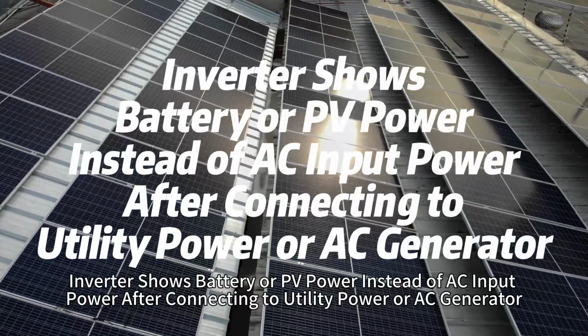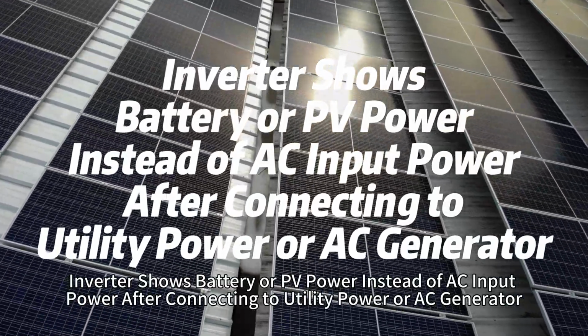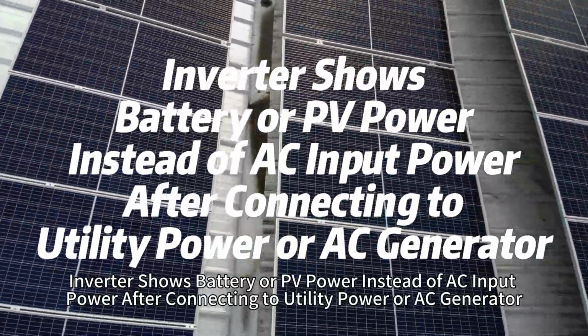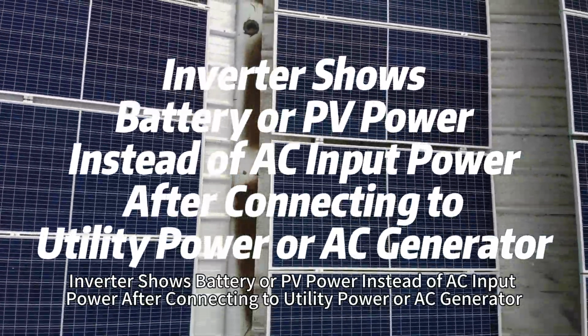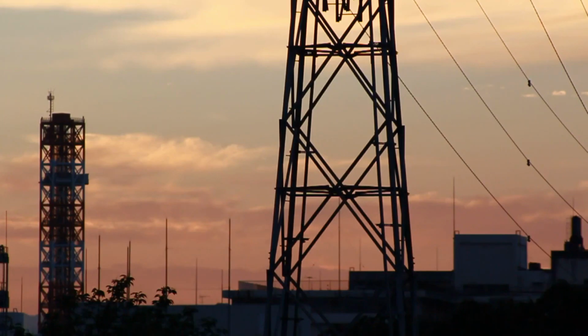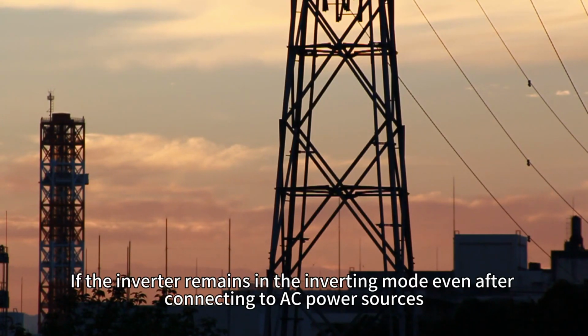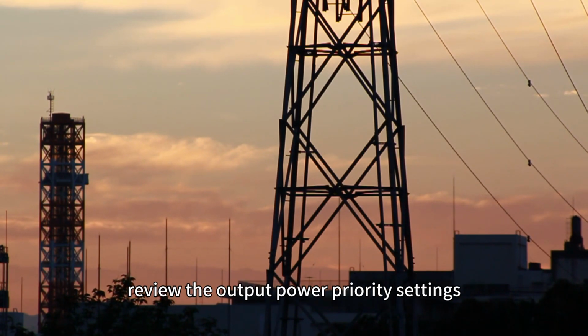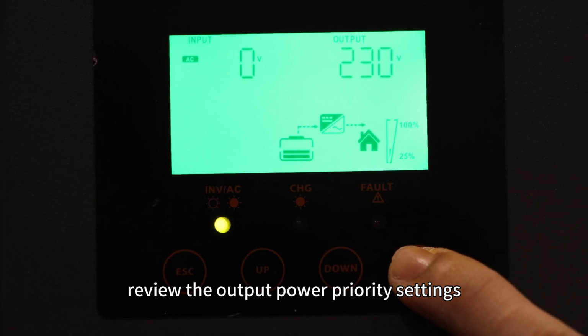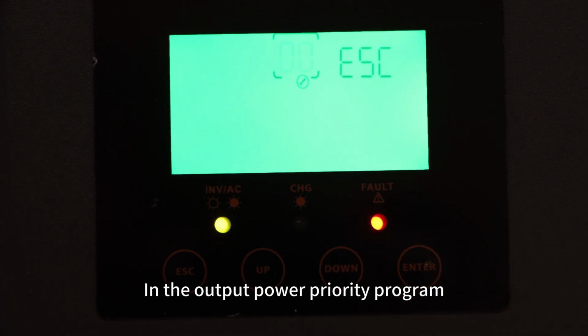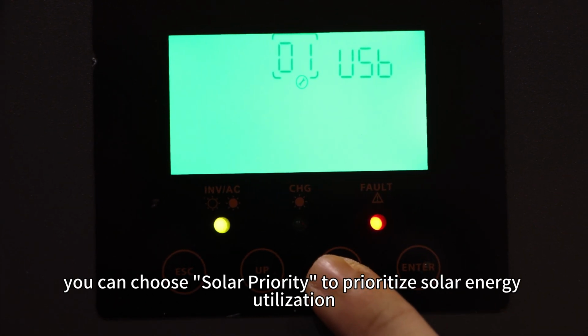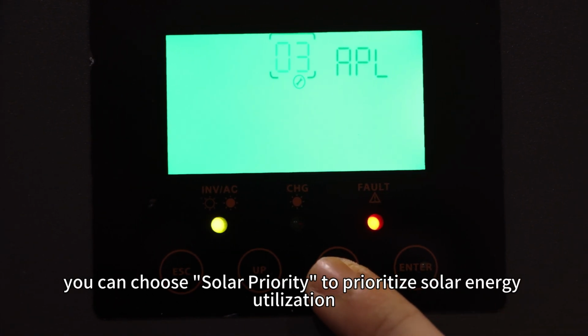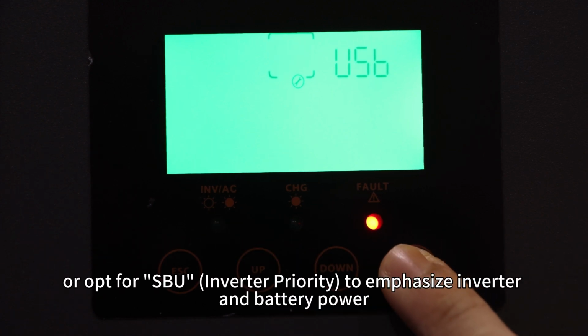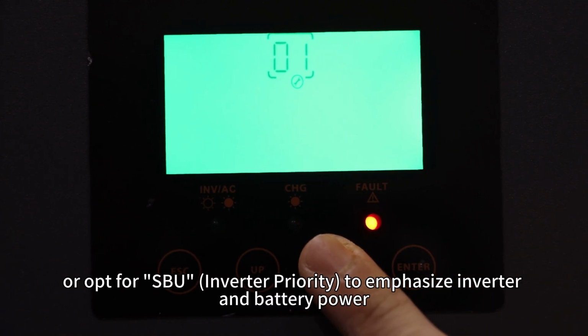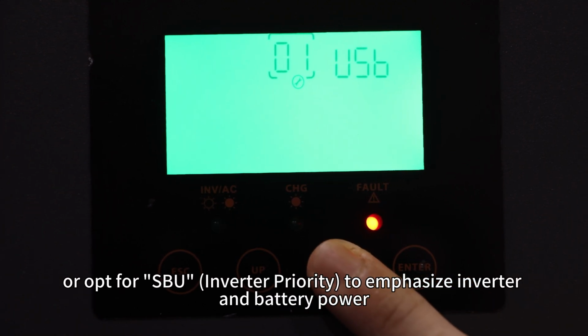Inverter shows battery or PV power instead of AC input power after connecting to utility power or an AC generator. If the inverter remains in the inverting mode even after connecting to an AC power source, review the output power priority settings. In the output power priority program, you can choose the solar priority to prioritize solar energy utilization, or opt for SBU to emphasize inverter and battery power.